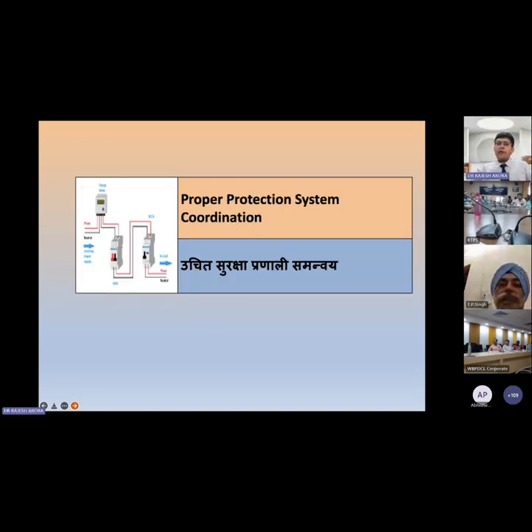Proper coordination. Everything is well placed. Proper ratings of MCBs are there. But when it comes to coordination, this is the painful area, one of the main causes of failure of protection systems. We feel everything is well in place, still some problem happens. Your protection system fails because of these reasons. Be careful.